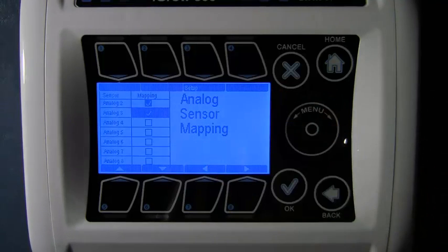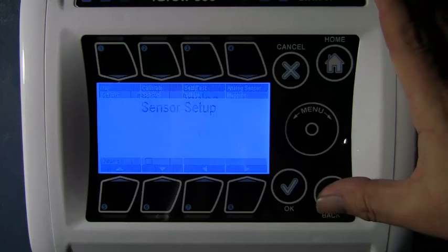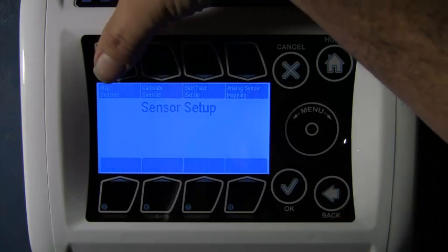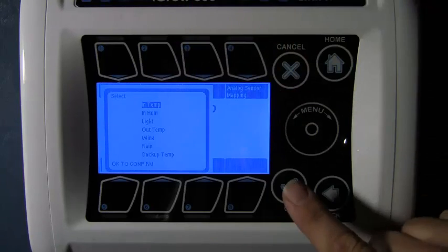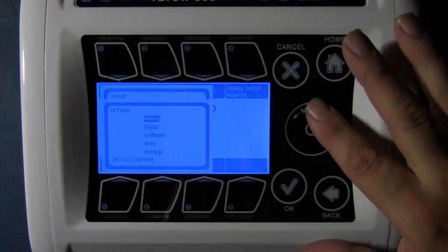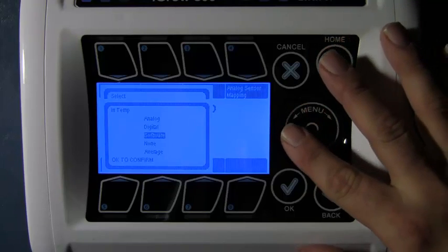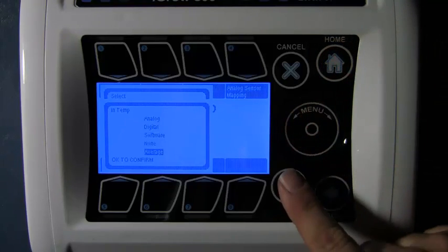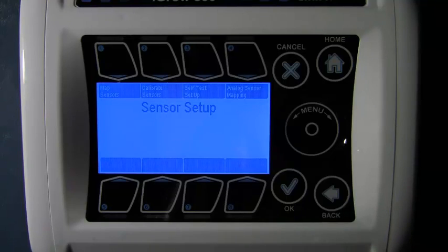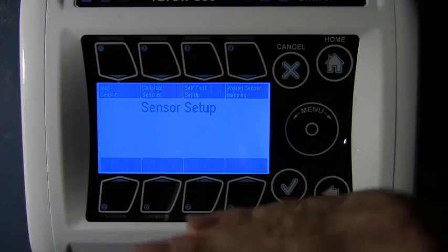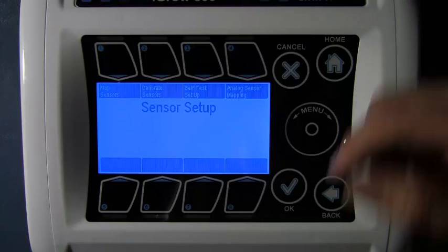If you have two sensors installed, both analog and both on separate sides of a large greenhouse, you can obtain the overall temperature average by taking those two analog sensors, go ahead and hit back, and then you want to map the sensor, the in temp, and then you want to go ahead and scroll down for the in temp to be average. And by doing this, it will average both sensors as one temperature reading.